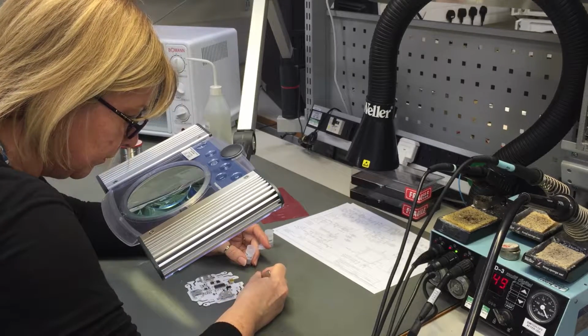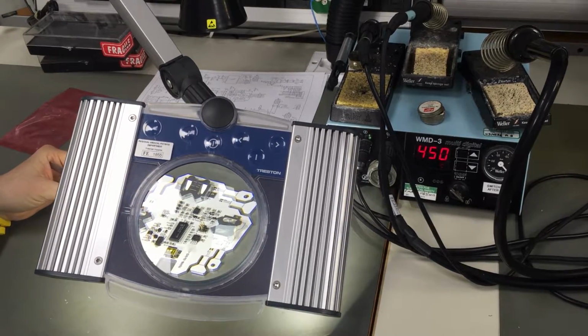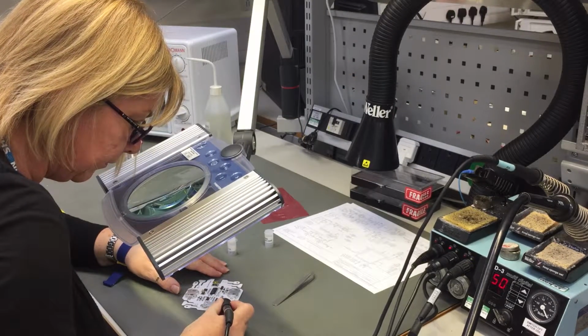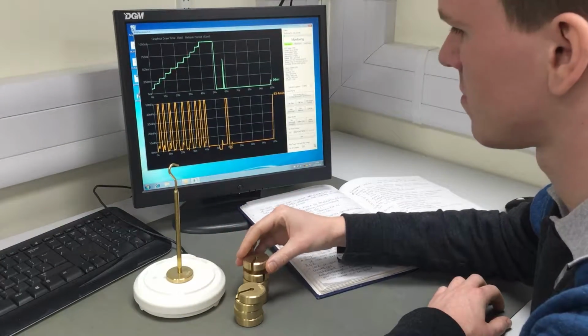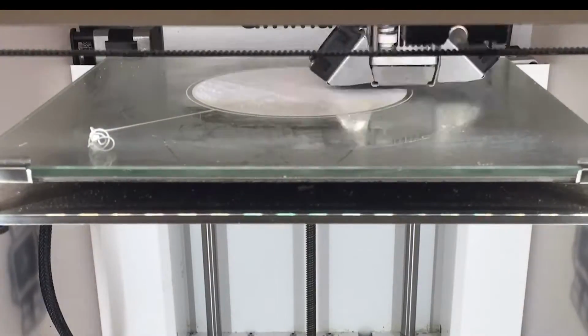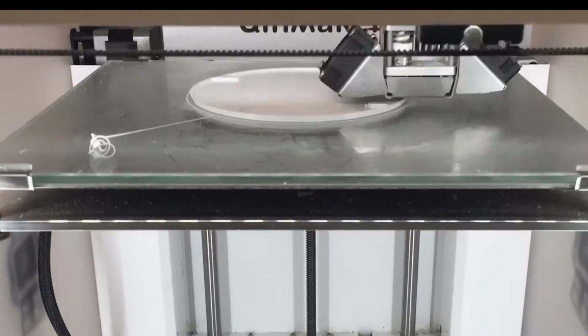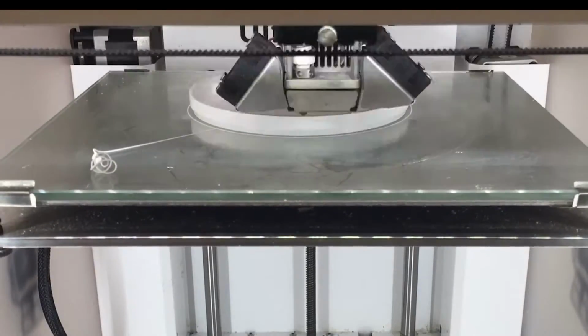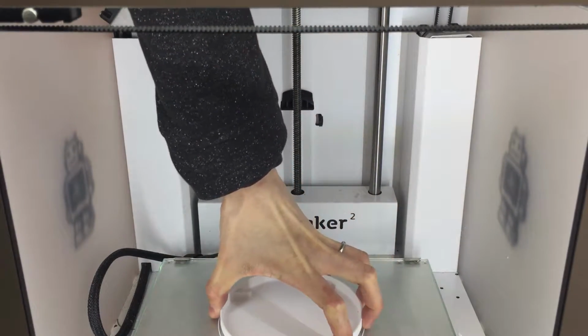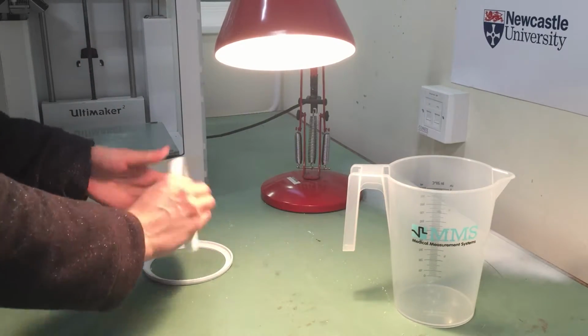We have integrated the sensing, electronics and power elements. Innovative methods like this will be required for redistributed manufacturing. They reduce component cost, weight and shipping cost and have not compromised the measuring performance. The new simplified case design can be manufactured using consumer 3D printing technology in only 4 hours compared to 24 hours for the original casing. With our new skeleton design, the final assembly is suitable for the layperson.